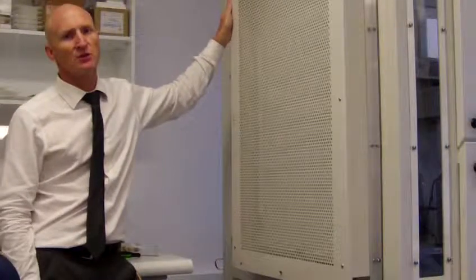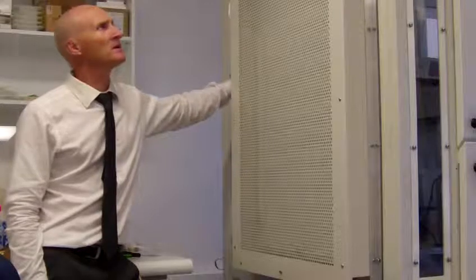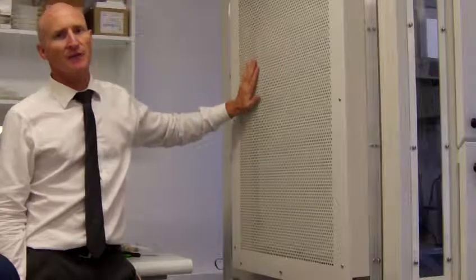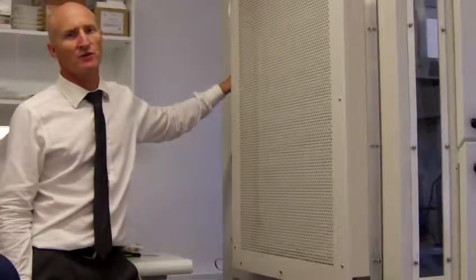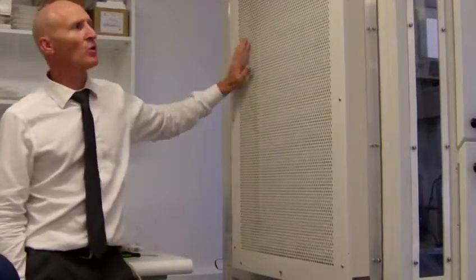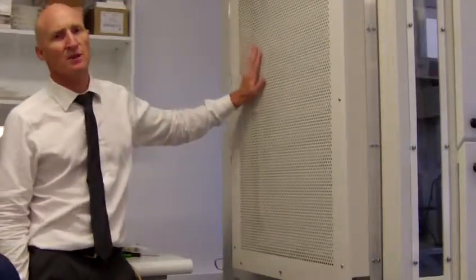They do vary, so you need to check your particular documentation to ensure there's enough air going to escape from here so that the unit doesn't get pressurized. Effectively, we're going to seal this completely, so all the air coming out of this hood comes through this HEPA filter.